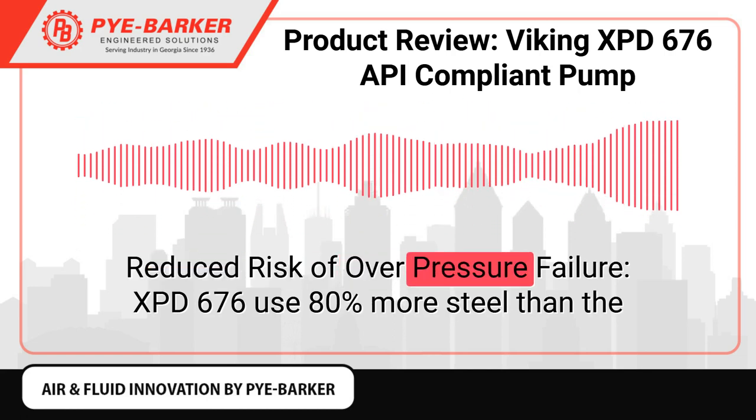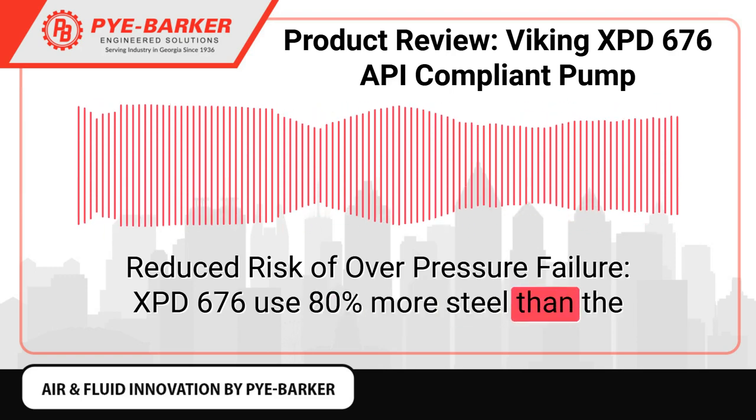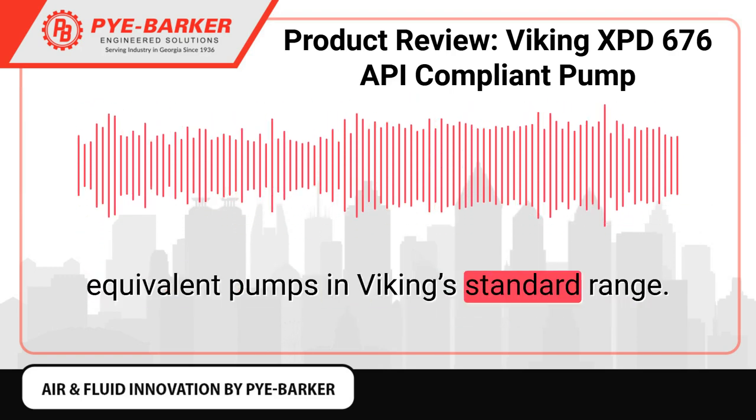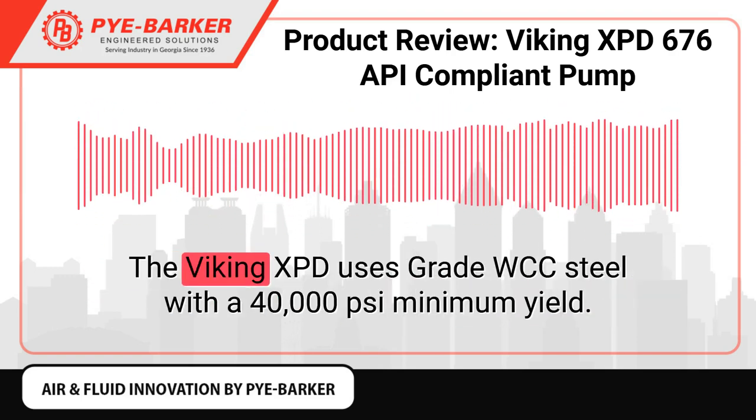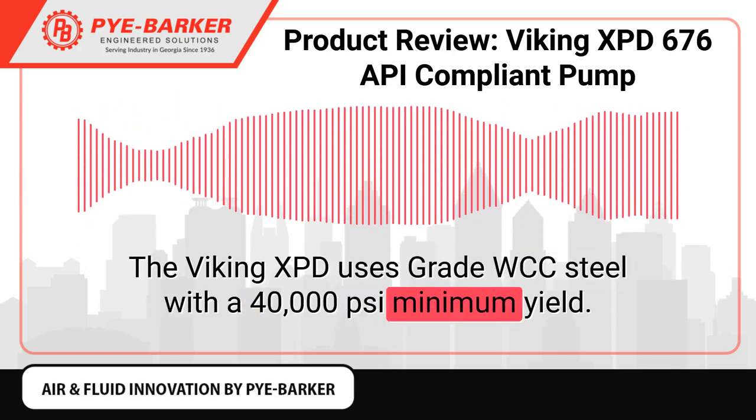Reduced risk of overpressure failure. The XPD 676 uses 80% more steel than the equivalent pumps in Viking's standard range. The Viking XPD uses grade WCC steel with a 40,000 psi minimum yield.